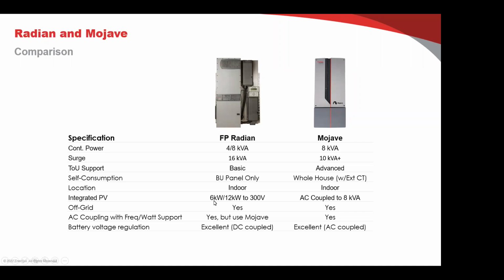Realistically, you're not going to do more than 6 kW because they're 100 amp charge controllers. So it's 100 amps times whatever your battery charging voltage is. Most battery charging voltages are 57 volts or less, which would be 5,700 watts or less. Could be, if you have a flooded battery with 63 volt equalization, and even then, I doubt we would go much above 6,000 watts. I think that's where the actual number is.